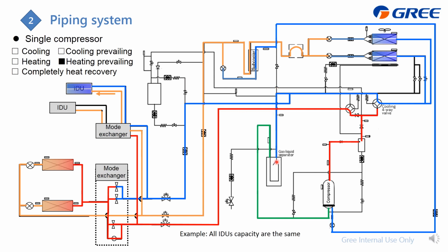just like this. And also you will find that there are 2 EXV here, and if the system finds that the outdoor capacity is too high, we will just fully close one of them to make heat exchange, which makes the balance between the indoor units the best.